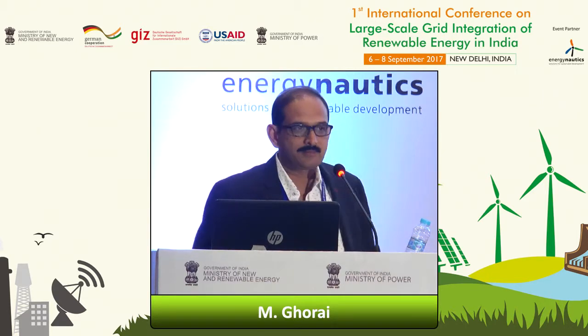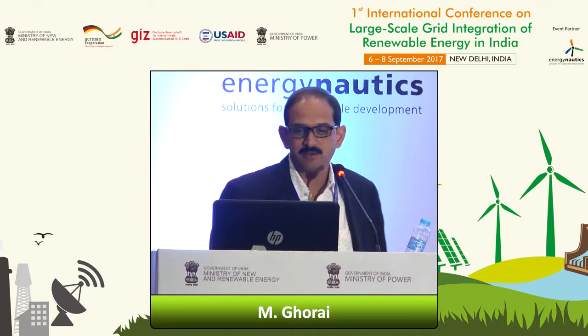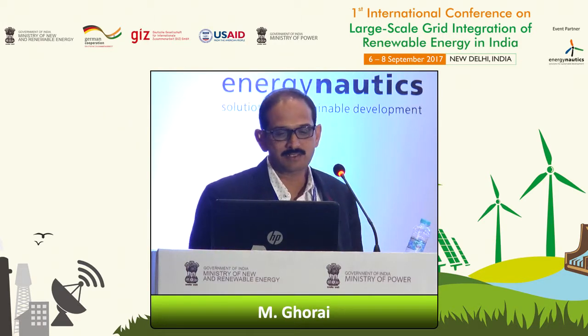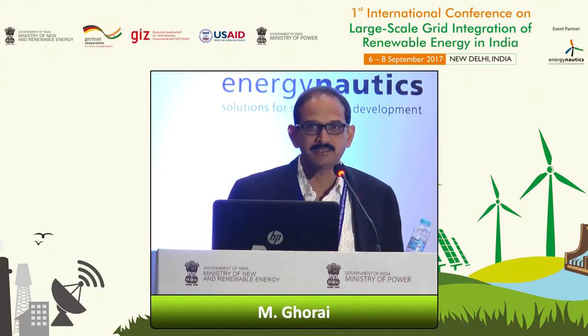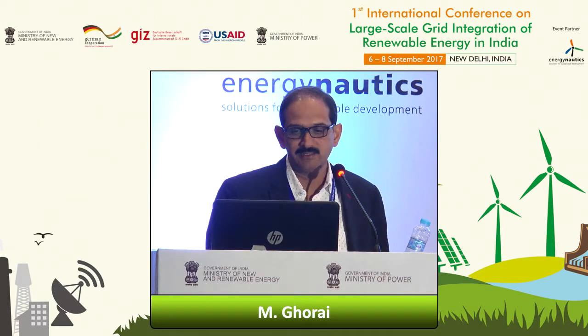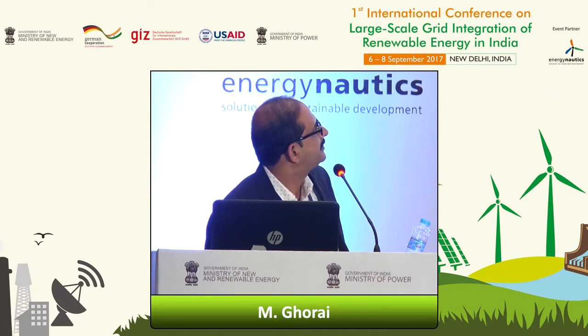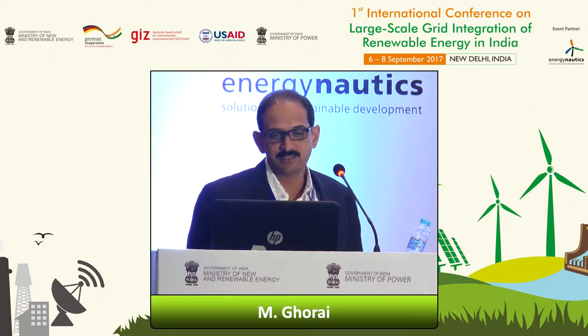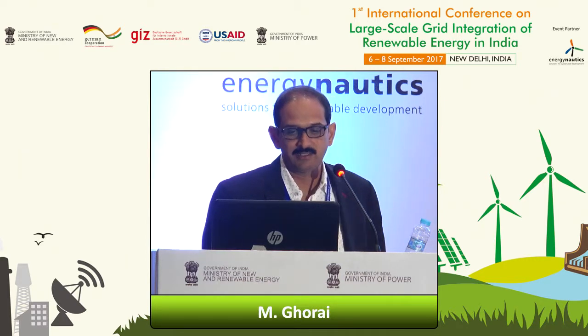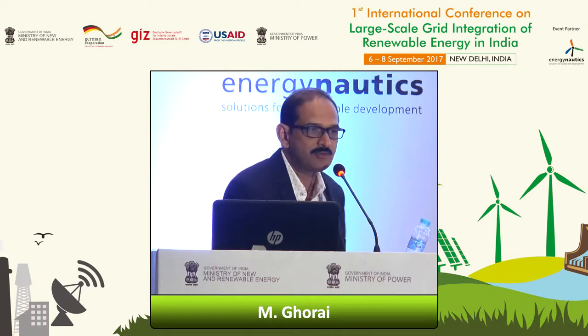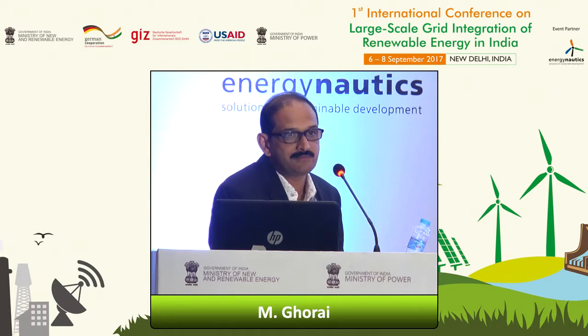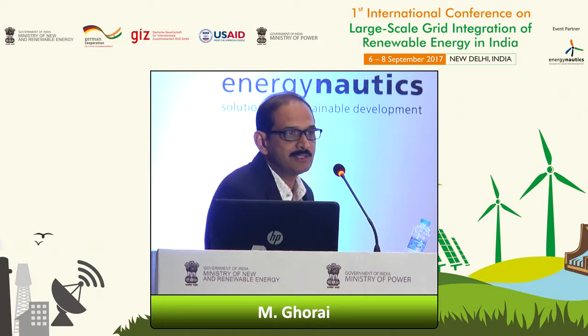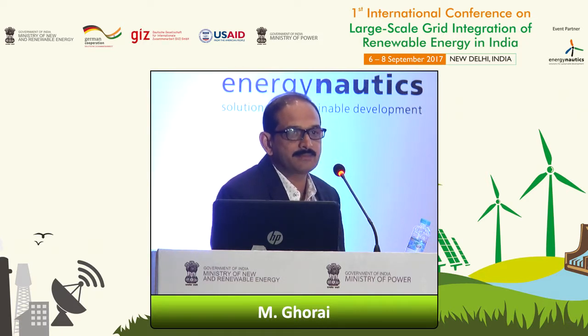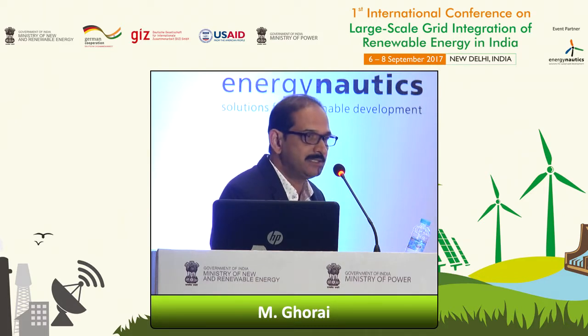Some important requirements of these grid codes talk about meeting the requirements at the point of common coupling. That could be on the high side of the transformer, at a transmission voltage level. Then when you talk about the reactive capability of the wind farm or a solar farm, they have some reactive capability. That's the one. Then there are some capacitor banks also installed in the power plants.